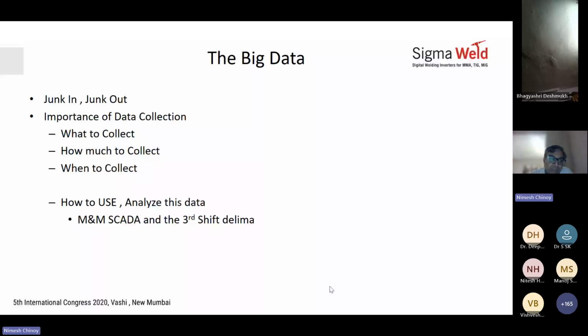After 2-3 months of installation, we had a meeting where the team told us the machine was down 29% of the time and asked how we could use this. I said, let's see the data. They pulled out their maintenance register and started discussing it. I asked why we were using that when we had a SCADA system - why not use that data instead? So we went to the machine, downloaded the data via USB, came back, and plugged it into the system. We saw that the machine data also showed 29% downtime, matching the register.